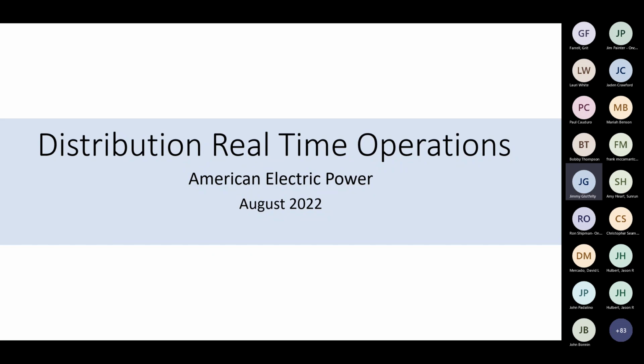So is that all inverters or just all Powerwall inverters? UL 1741 SB applies to all inverters that are certified. It is a United States standard. That doesn't mean all historical certifications of 1741 have those capabilities. There's UL 1741, from 2002 I believe, then UL 1741 SA around 2014, and now UL 1741 SB, from the end of last year.